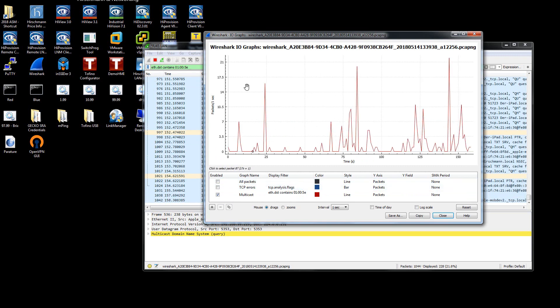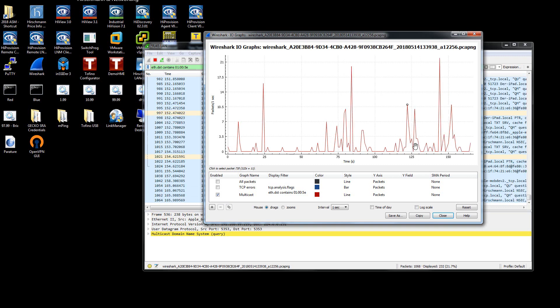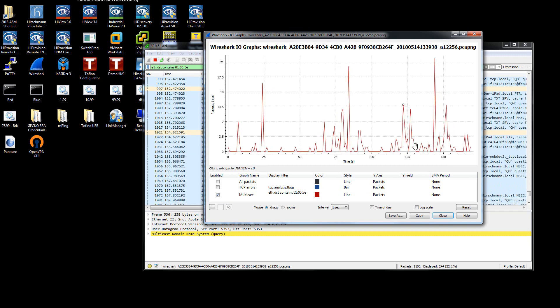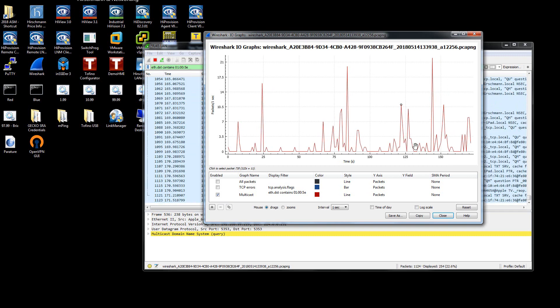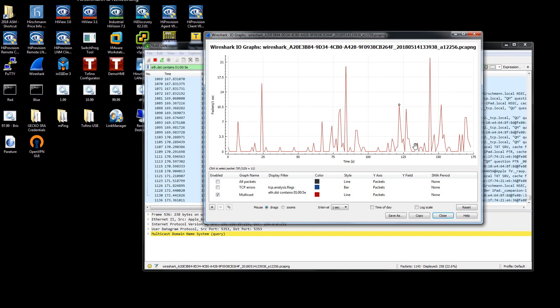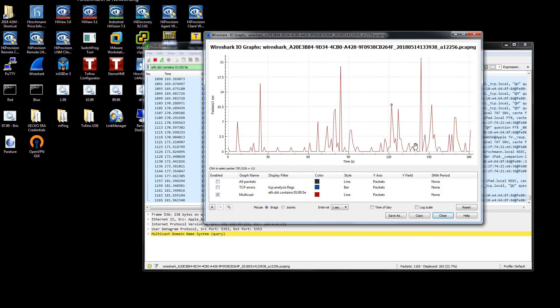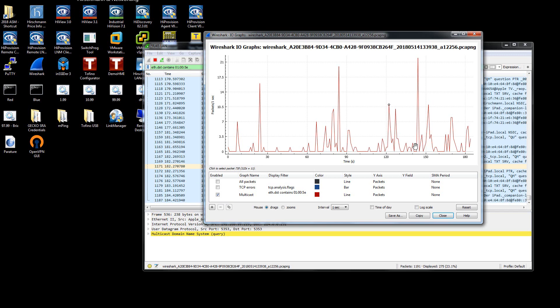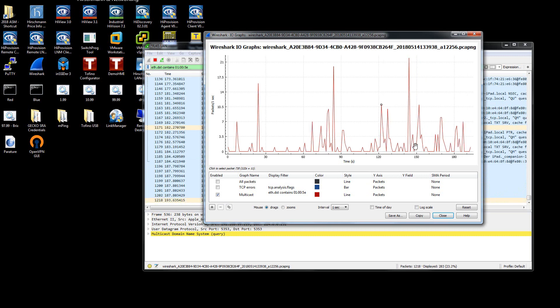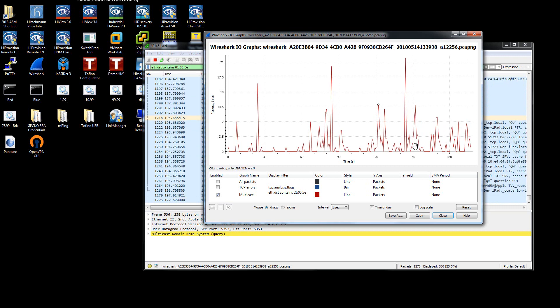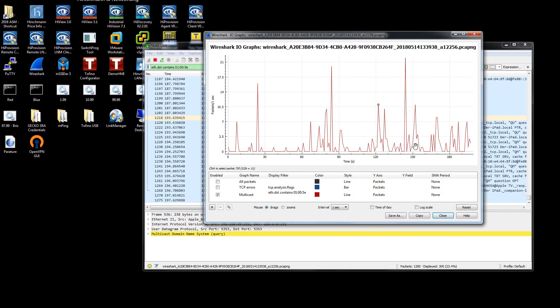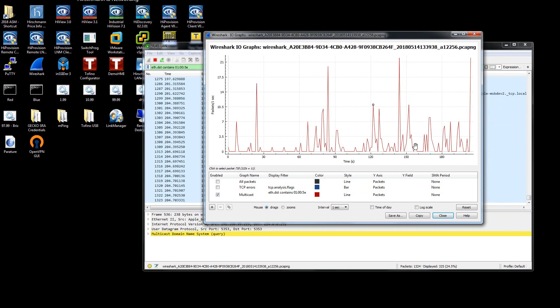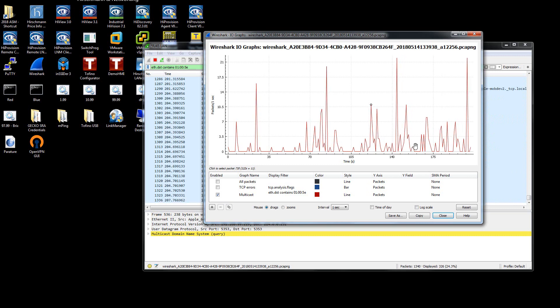So as an example, here I'm showing only multicast traffic. Anything that is less than 100 is good—100 being 100 packets per second. Anything beyond 100 packets per second is excessive and should be filtered. Depending upon the PLC or controller vendor, the various devices are able to accept and process varying degrees of packets per second. But if you think about it, an Ethernet switch is capable of processing about 2 million packets per second, which is a whole lot more than any automation device can possibly tackle.